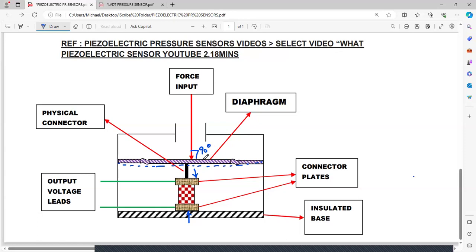Pressure per unit area acts at a right angle of 90 degrees, not any other angle. This force or pressure acts on the diaphragm, causing it to be depressed inwards. When depressed, the physical connector presses onto the piezo crystal, and correspondingly you get a voltage output. This voltage output is sent to an electrical circuit where it is converted to tell you the pressure acting on the diaphragm. It is calibrated to give you pressure in bar, MPa, PSI, whatever the calibration requires.